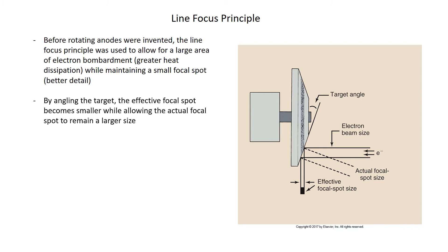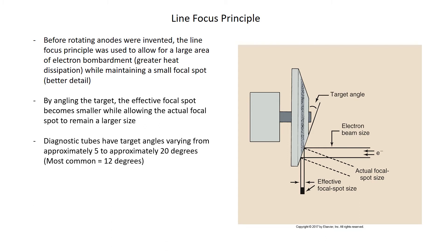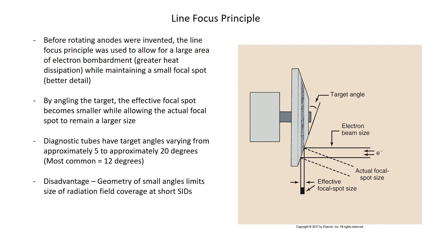By angling the target, the effective focal spot becomes smaller while the actual focal spot remains larger. Diagnostic tubes have target angles varying from about 5 to approximately 20 degrees, with the most common being about 12 degrees, though there is variance depending on the author. The disadvantage is that the geometry of small angles limits the size of the radiation field coverage at very short SIDs, which is why you can't angle too much.